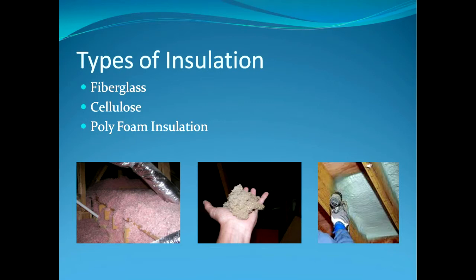For instance, fiberglass insulation is light, cheap, and has a good R value at an average of 3.5 R value per inch. But fiberglass doesn't insulate very well if exposed to outside air currents. Also, exposure to large amounts of water renders the insulation worthless.